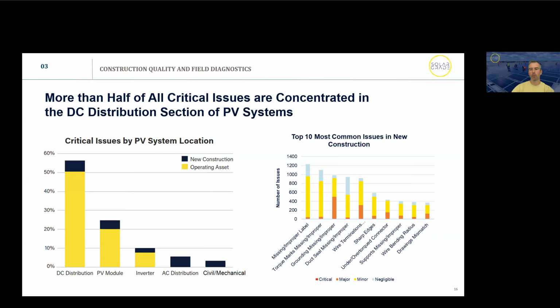When we look at where these issues are located within the system, over 50% of critical issues are located in the DC distribution, basically anywhere from the solar module to the inverter - connectors, strings, cabling, DC harnesses, grounding, combiner boxes, cell combiners, etc. The DC distribution is the weakest link in the chain and is typically overlooked and not well thought out, due to its low capex compared with larger equipment like modules, inverters, or trackers.